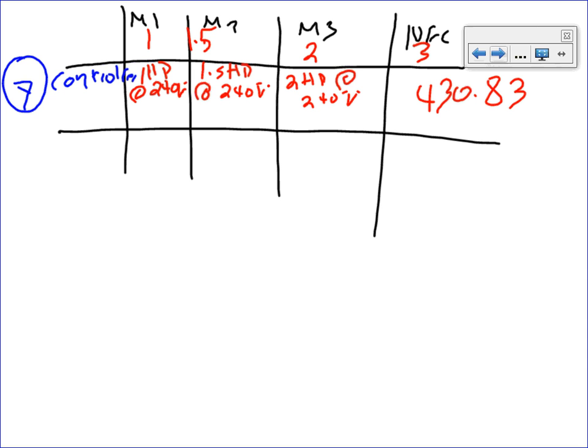Okay, then for those of you who have DeWalt, I want you to go with me to DeWalt page 6-4. We need to size the controller: NEMA rating of AC motor starters in amps per horsepower, phase and voltage. We rate the starters based on NEMA, National Electrical Manufacturers Association, NEMA 00, NEMA 0, all the way to NEMA 9. Can you see it goes from 00 at the bottom all the way to the top, 9?